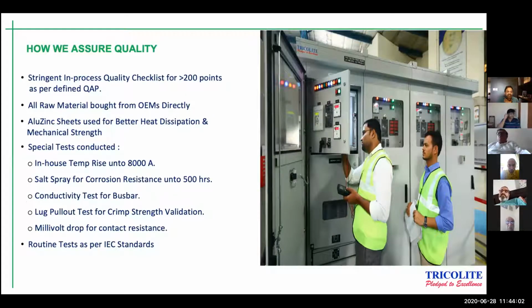This is how we ensure our quality. Some of the key quality tests we have in-house and use regularly is the temperature rise test up to 8000 amperes. We do most of our temperature rise tests for clients in-house, some chargeable, some free of cost, depending on how the commercial modalities work out. We have a facility that can test up to 8000 amperes. We haven't tested any up to that, but we've done a 5000 ampere temperature rise test for DMRC within our plant.